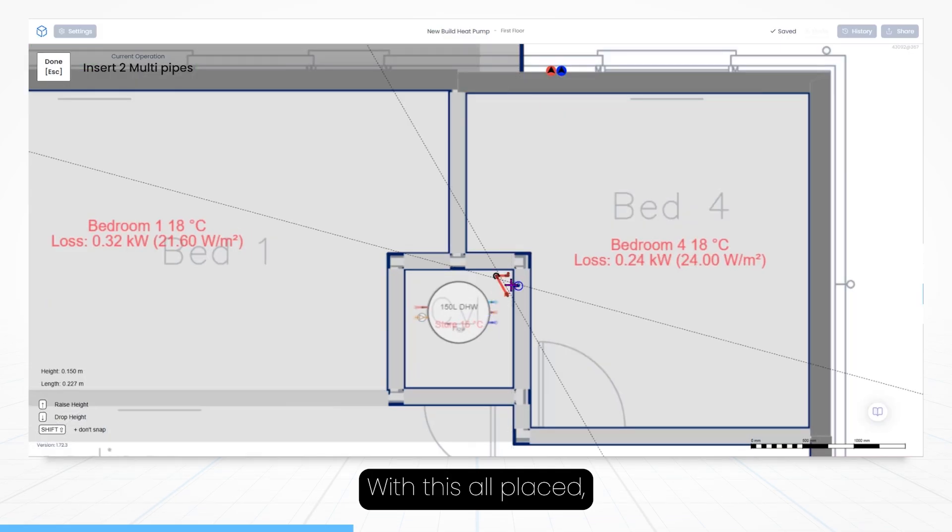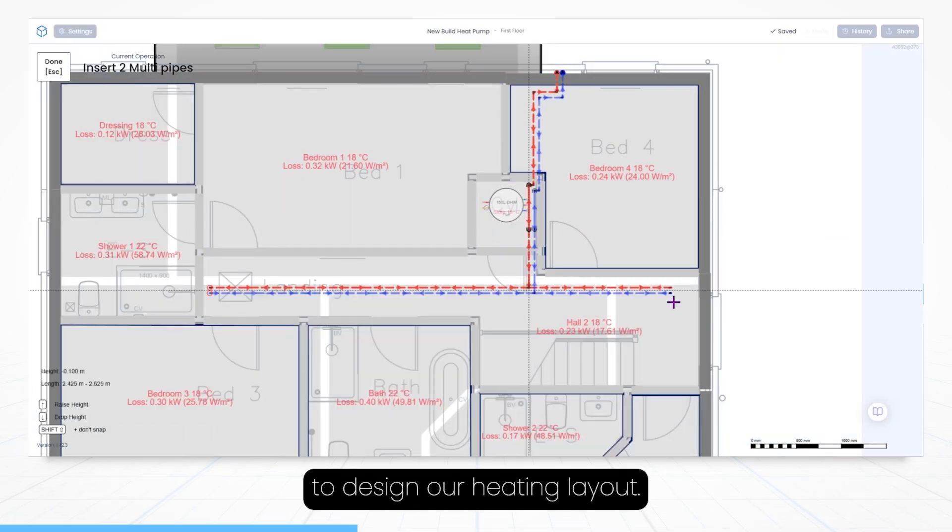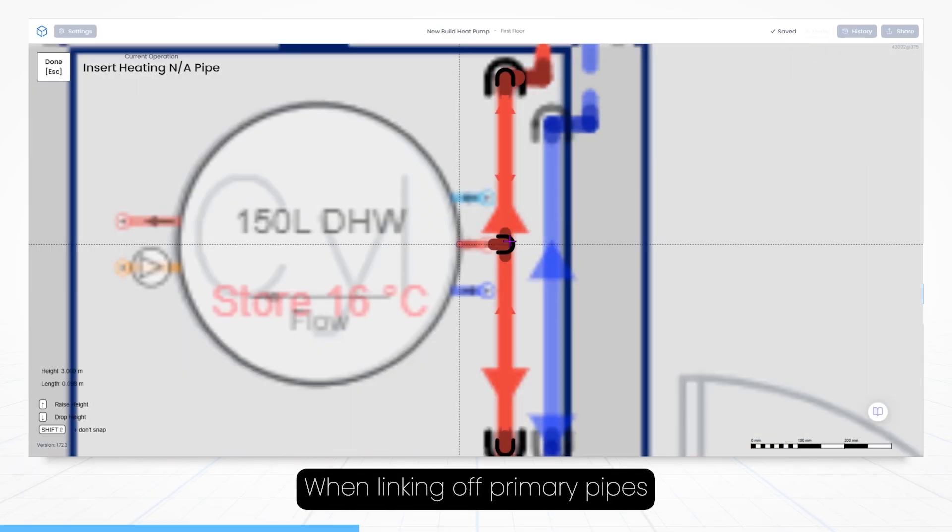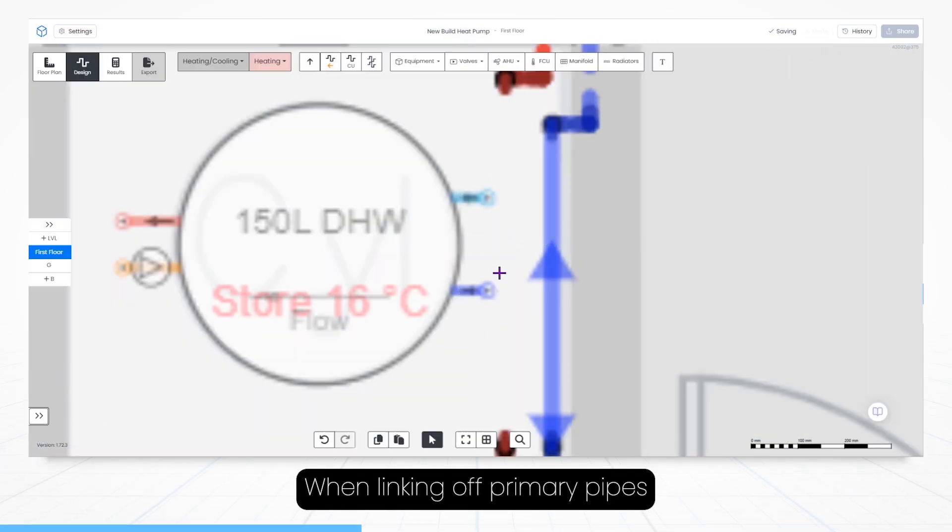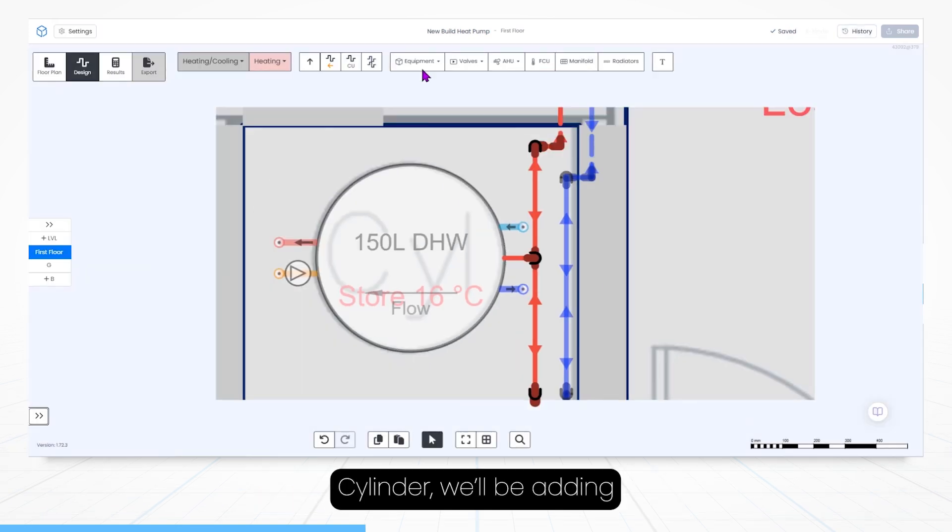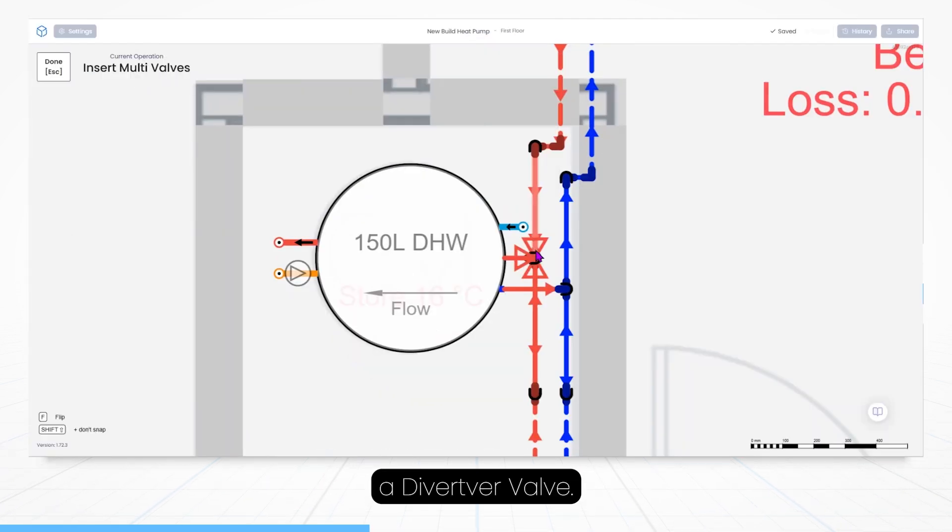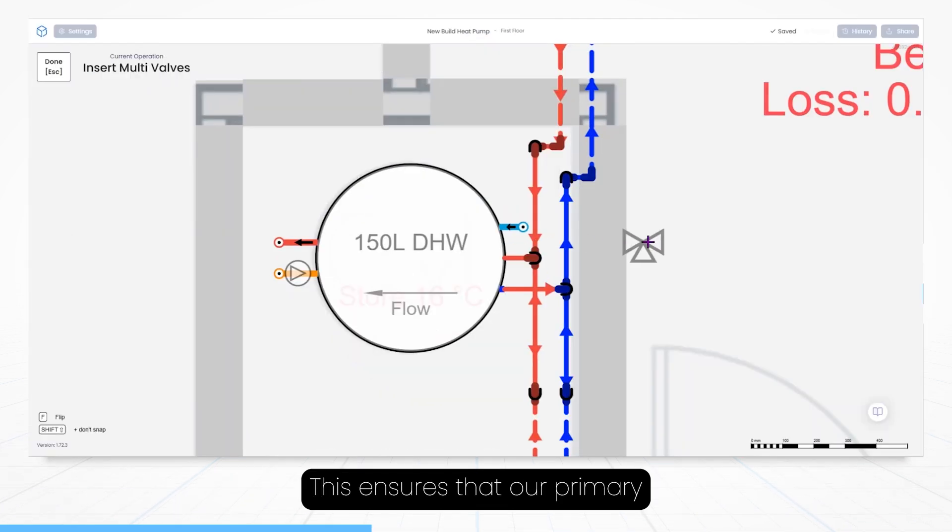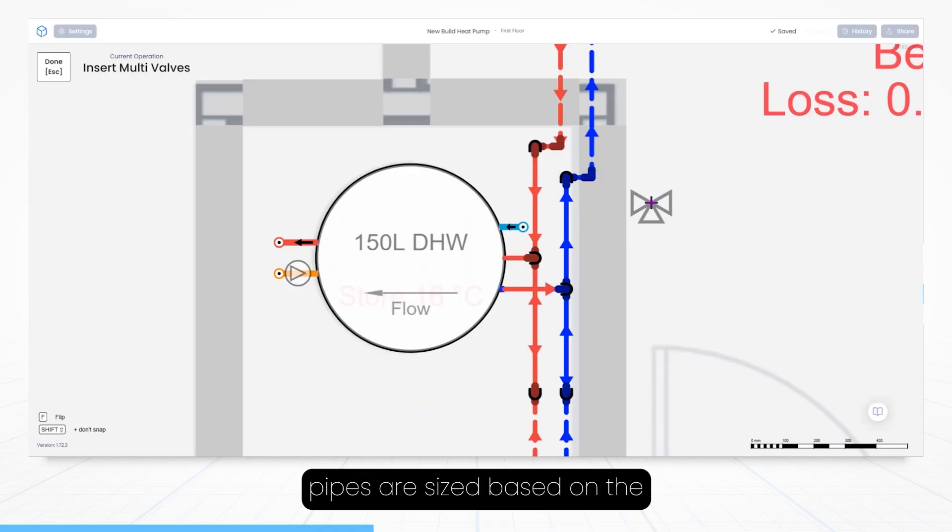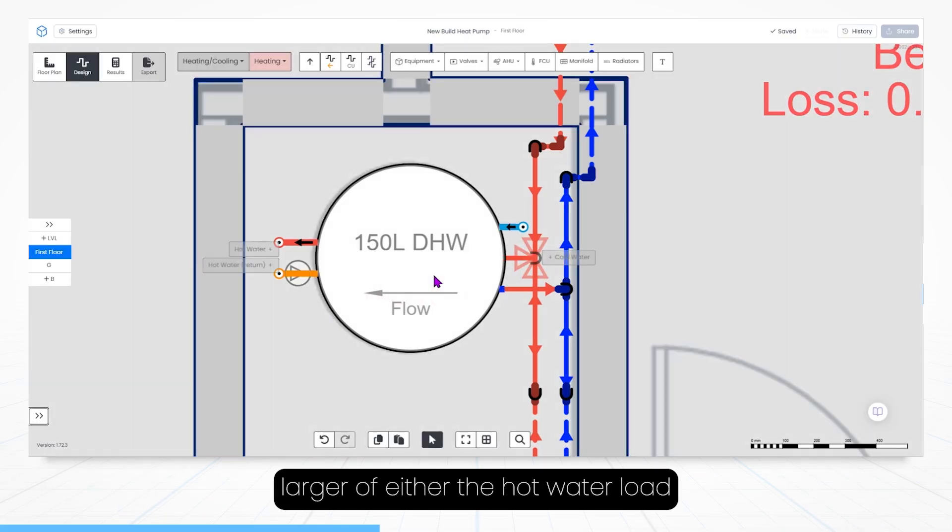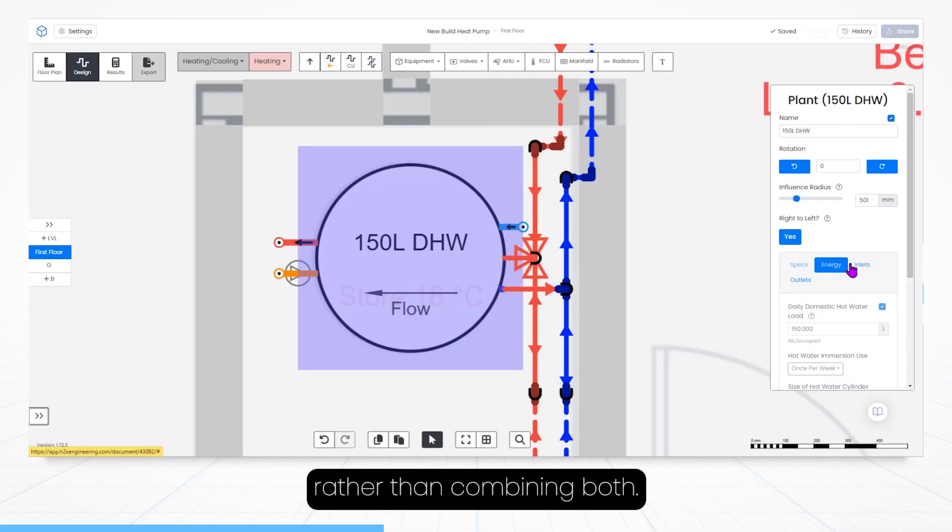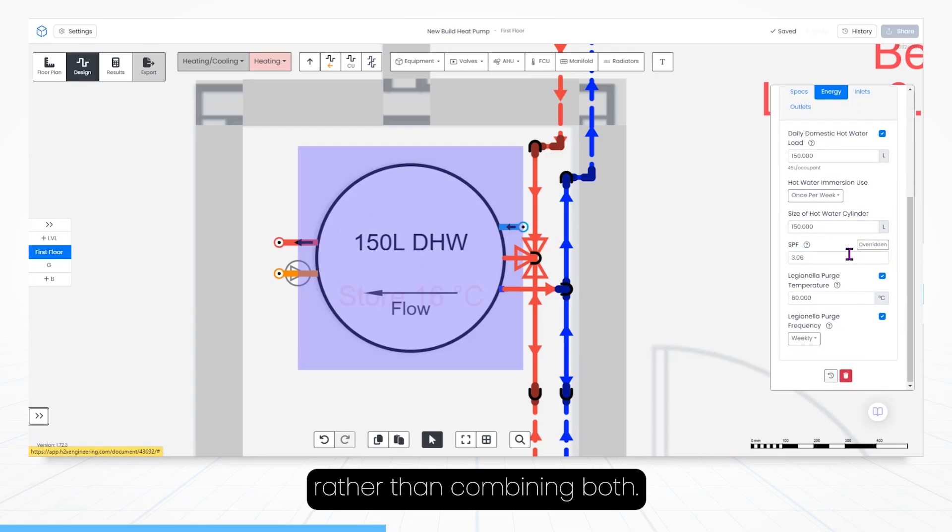With this all placed, now it's time to design our heating layout. When linking our primary pipes from our heat pump to our hot water cylinder, we'll be adding a diverter valve. This ensures that our primary pipes are sized based on the larger of either the hot water load or the space heating load, rather than combining both.